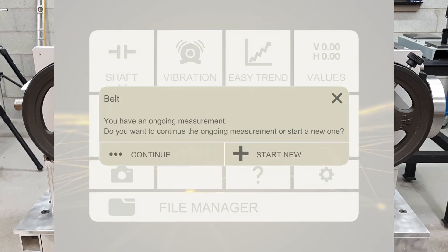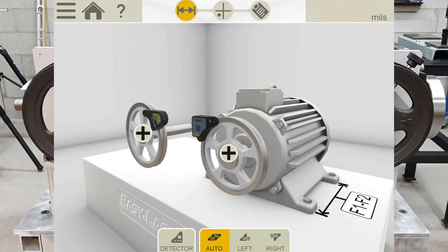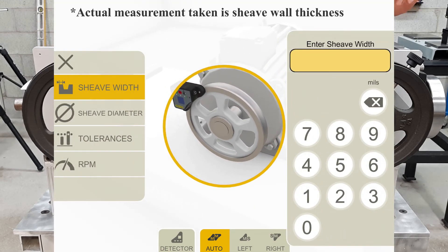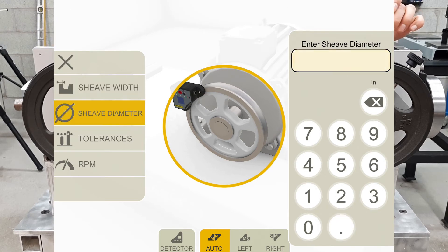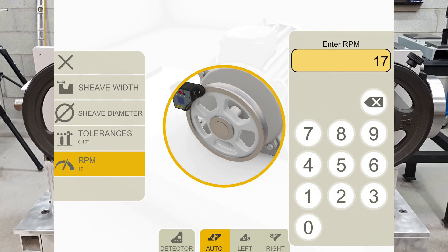When going into the belt alignment program, we can see from the start that the alignment process is shown at the top of the screen with icons. Currently we are on the distances screen, where I can enter the distance between the machine's feet as well as some other important data. The next icon shows the measurements screen — where we take the actual measurements — and finally the documentation icon, where we create a report. Tapping the motor plus symbol, we can enter the sheave width, which will automatically compensate for mismatched sheaves — we'll discuss this more in detail later. We can also add the sheave diameter, the tolerances and the RPM; we will input 1725, which is the most common RPM.